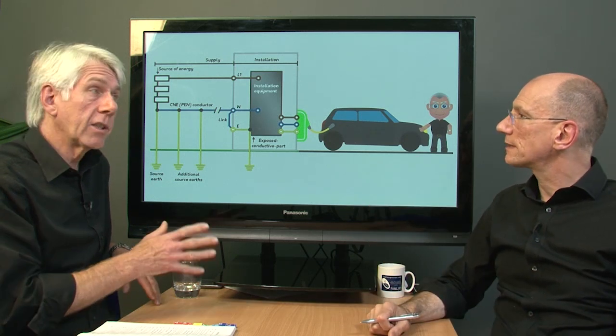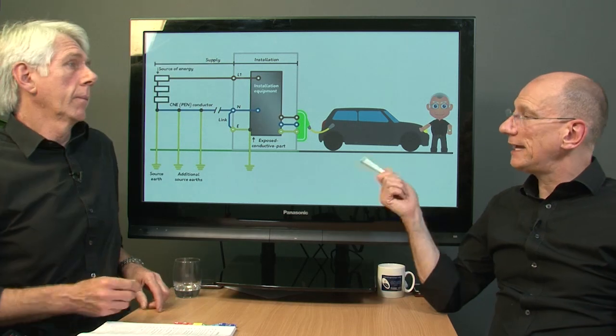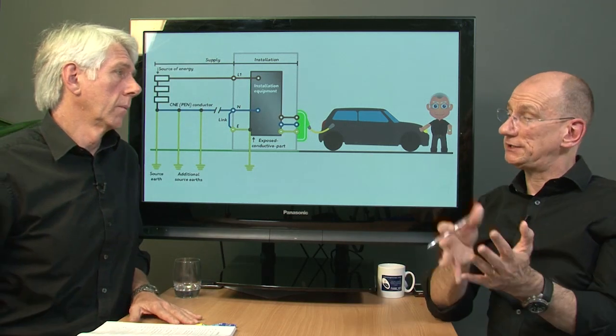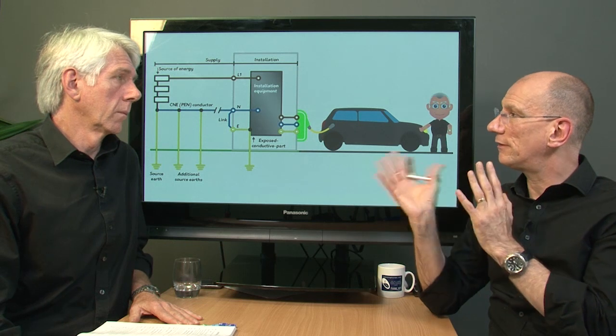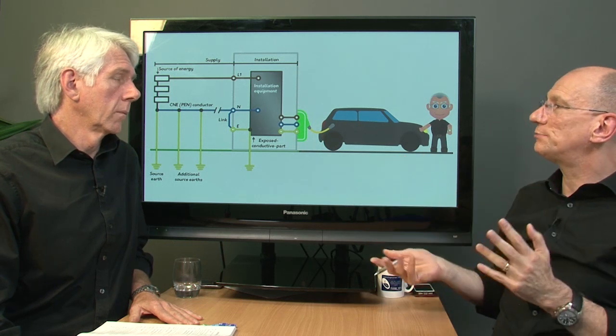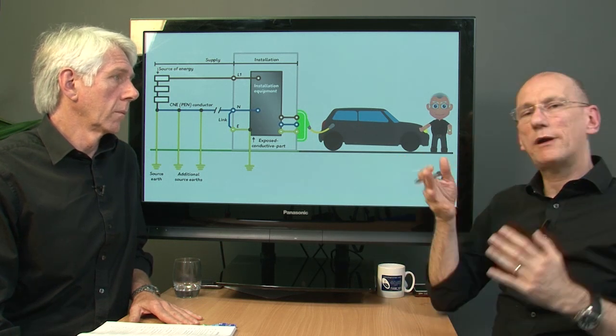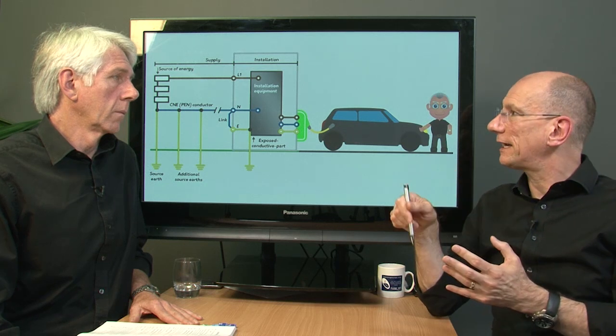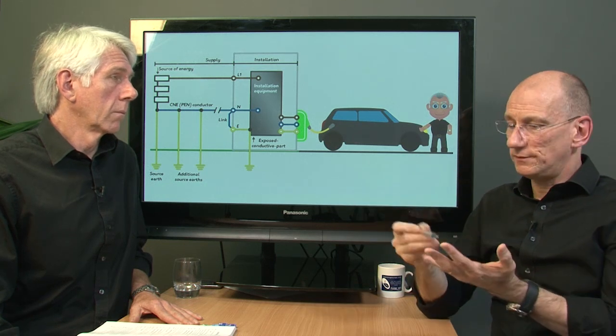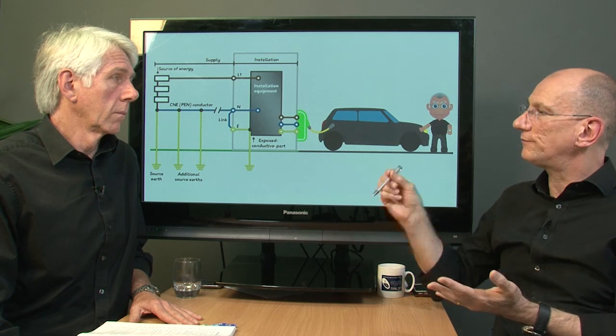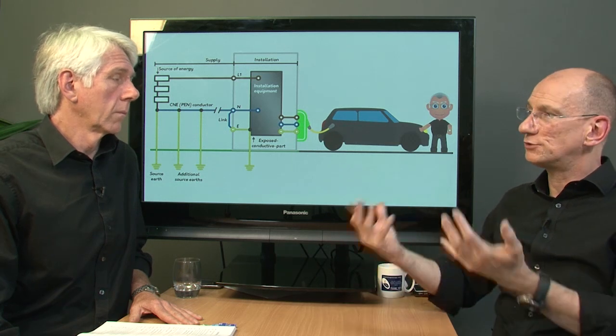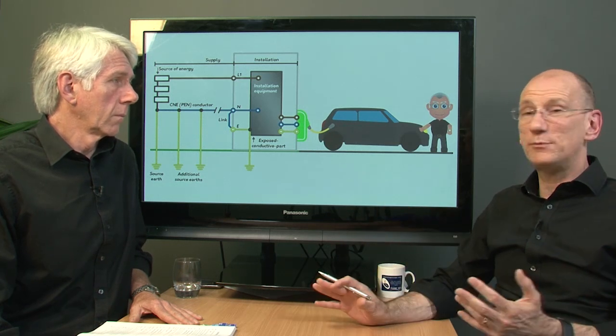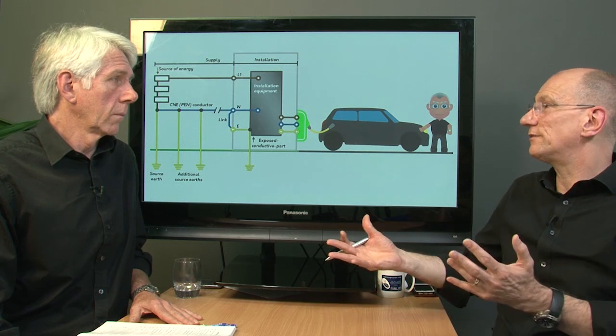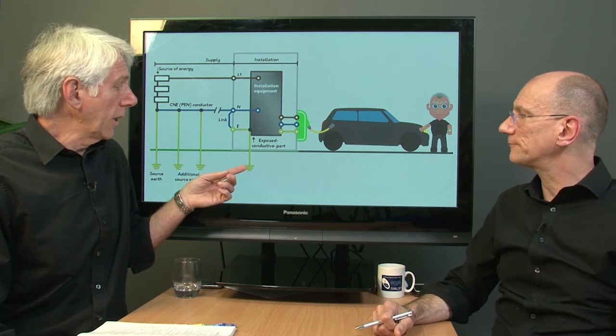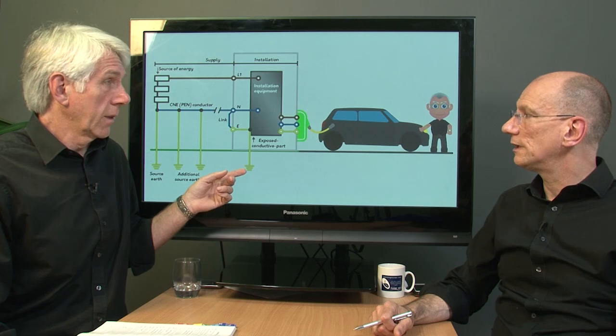But it has its own problems, doesn't it? Yes, whether we're touching on TT or the supplementary earth electrode, there are a number of interested parties that do worry about the banging in of an earth electrode. You run the risk of hitting a service pipe, gas, sewage pipe or something like that. And never mind the fact that you've got maintenance, because no one's ever going to look at that, and actually maintaining the required resistance on this is not the easiest thing.